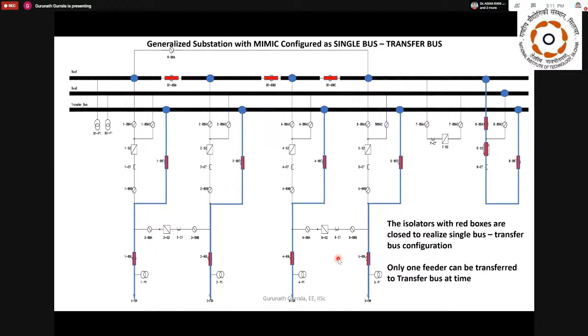Once you transfer this feeder to the other bus, then even if you try to transfer the other feeders to the transfer bus, it should not allow. This is called an interlock mechanism, which you need to code into your bus control unit. This is a practical aspect which you will learn from this kind of system. So either way, I'm just showing all these things, and these kind of things can be done.